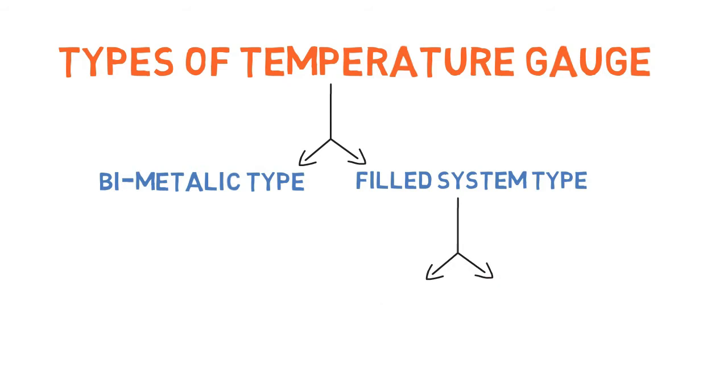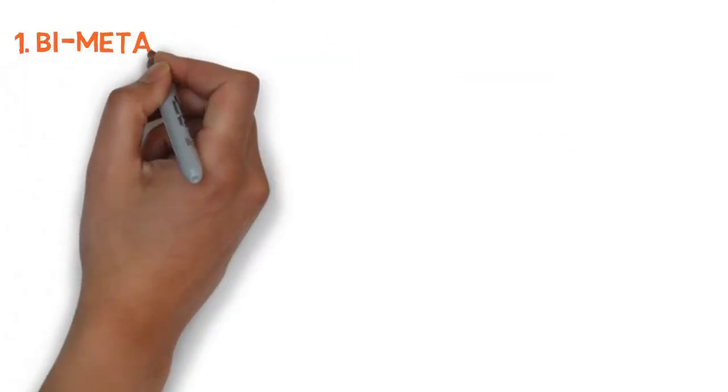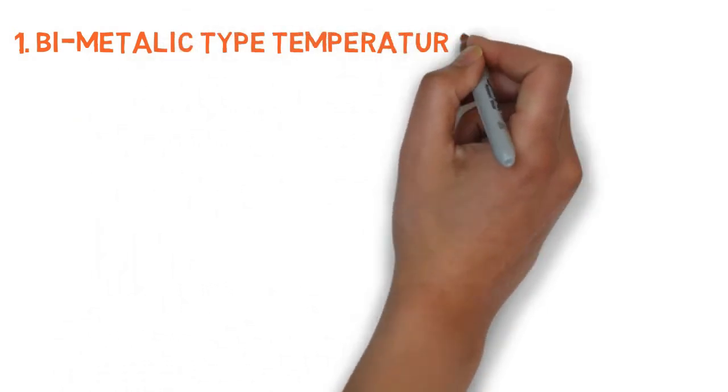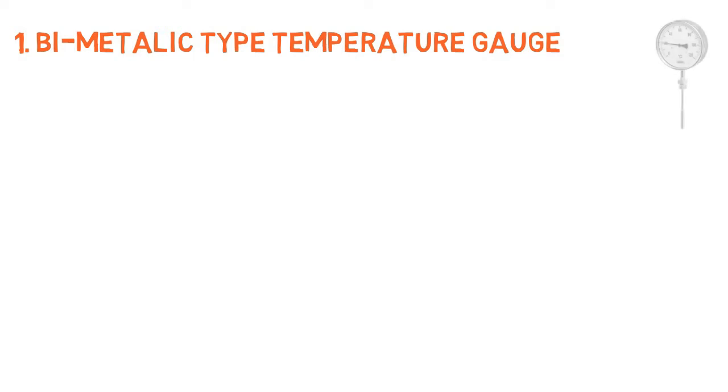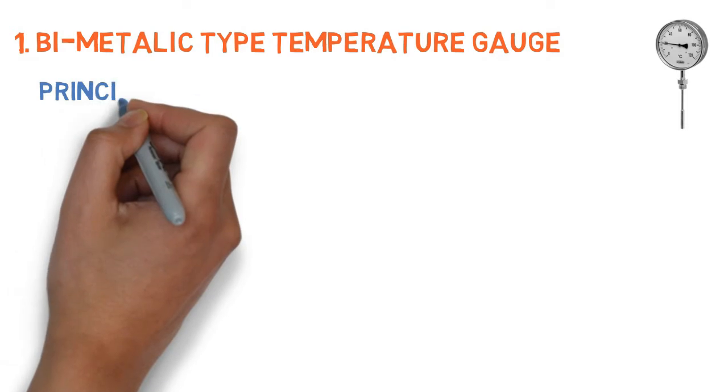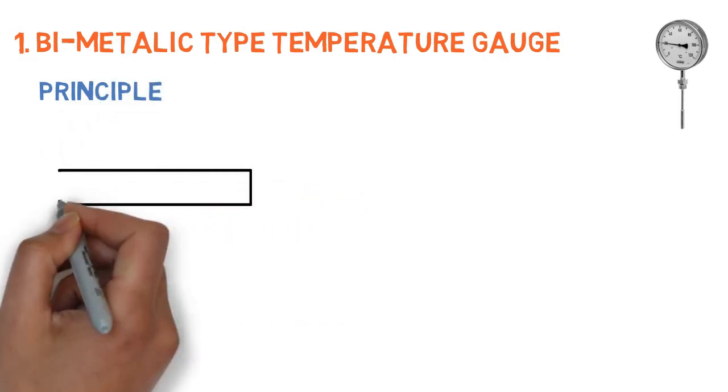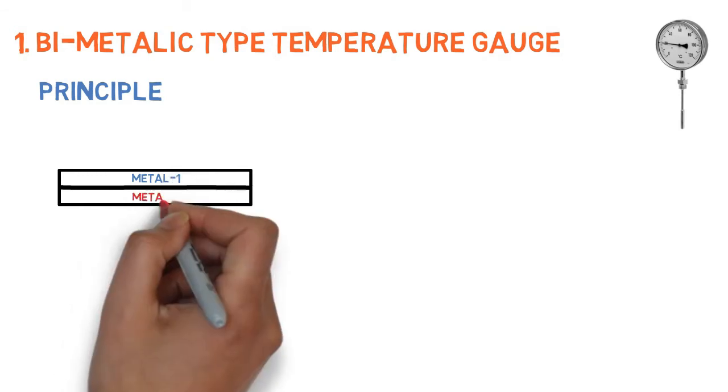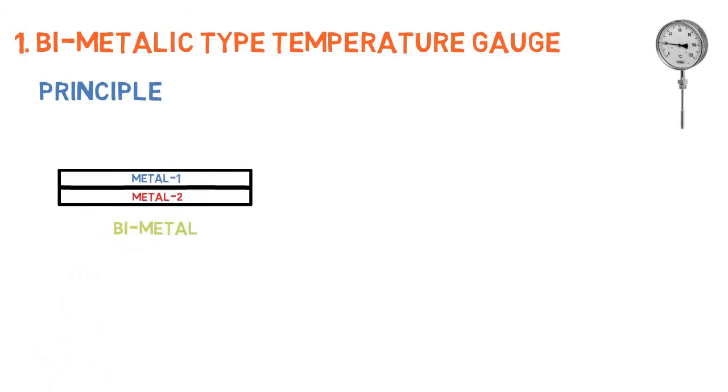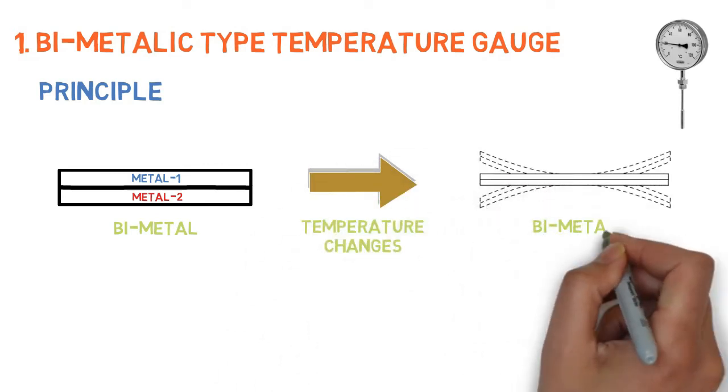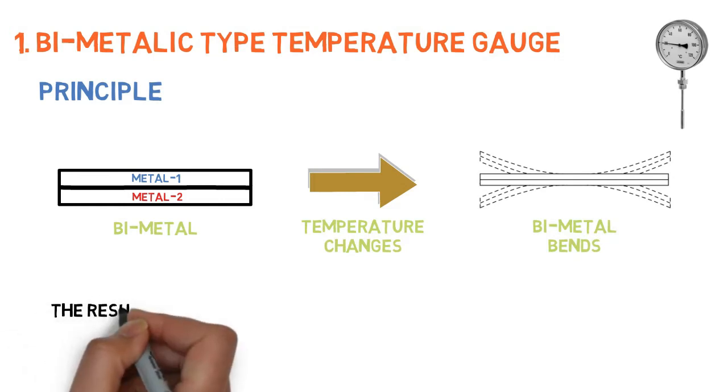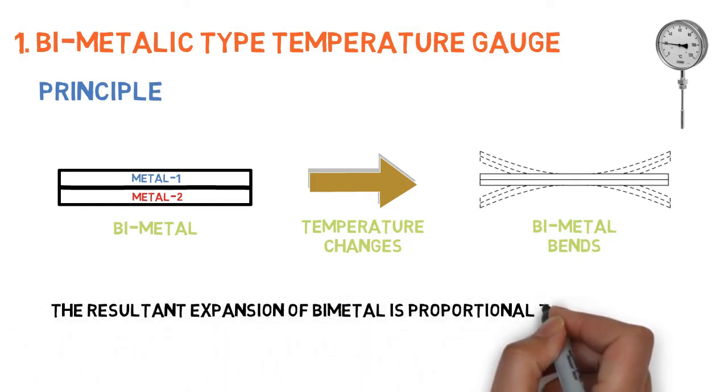The types are liquid filled type and gas filled type. Now we'll see about bi-metallic type temperature gauge in detail. It works on the principle of thermal expansion. Two metals having different coefficients of expansion are joined to form a bimetal. When there is a change in temperature, the bimetallic strip bends. The resultant expansion of bimetal is proportional to temperature.